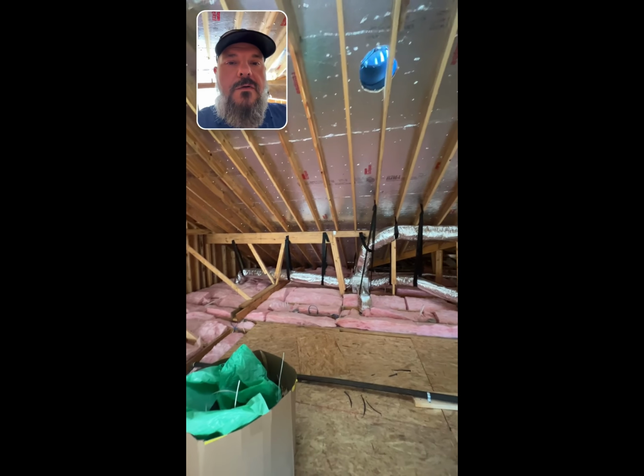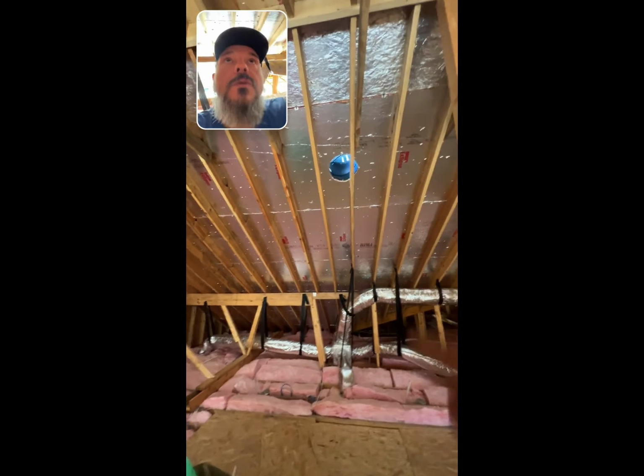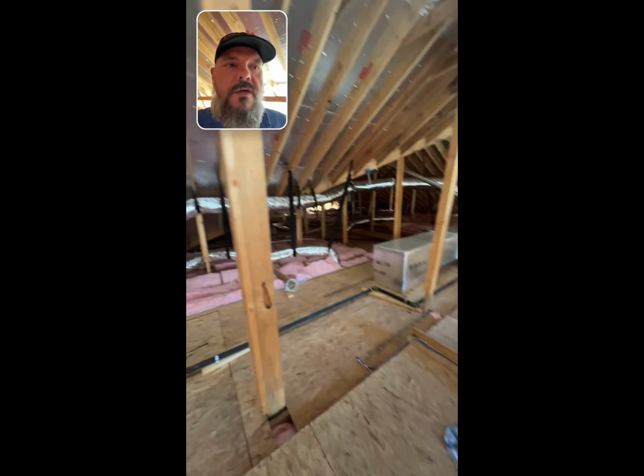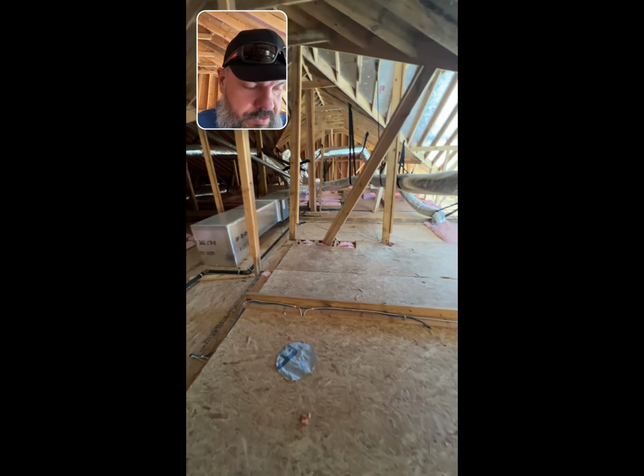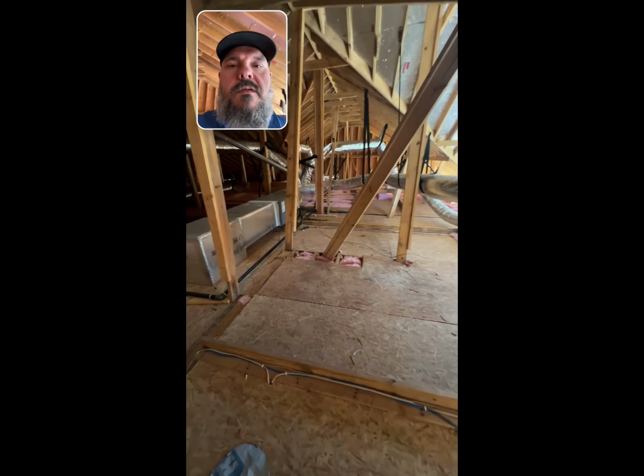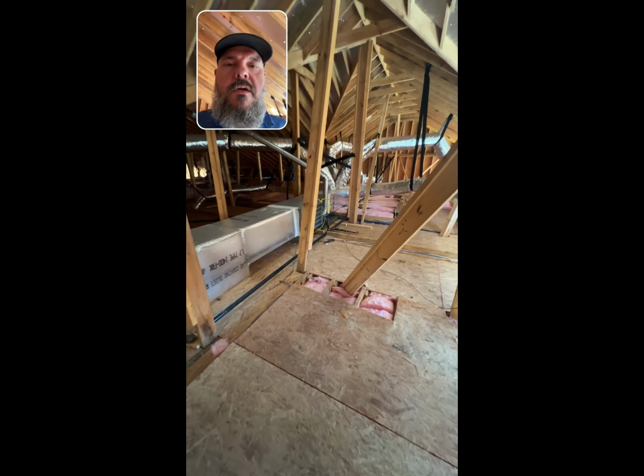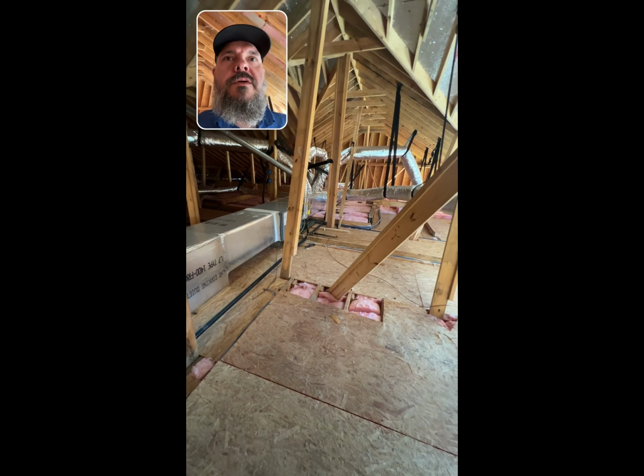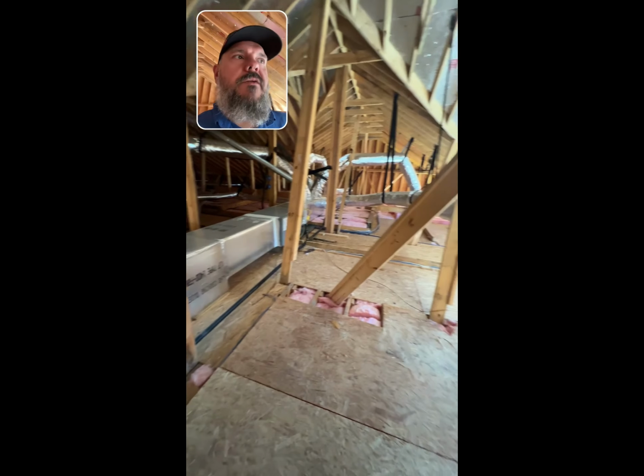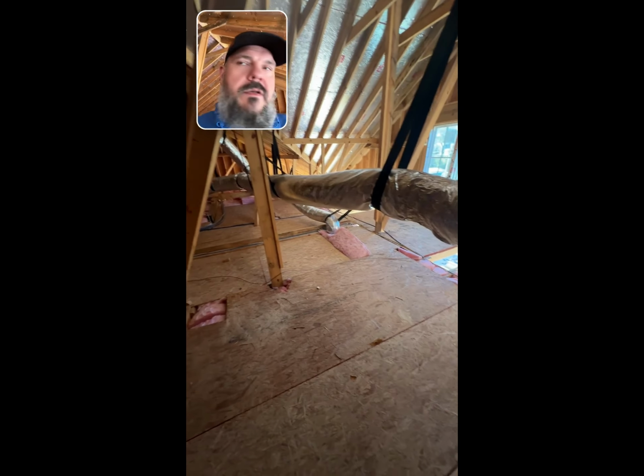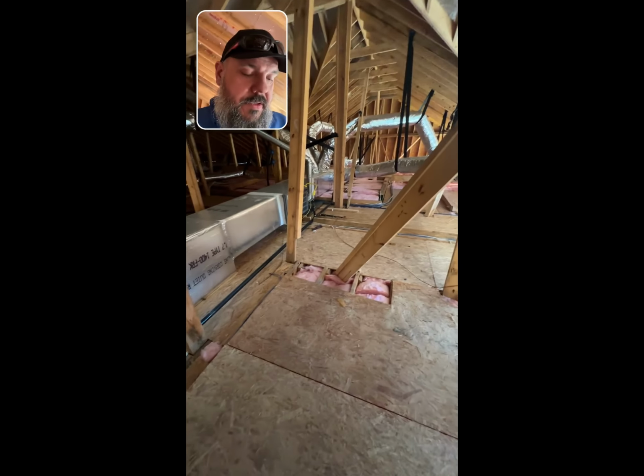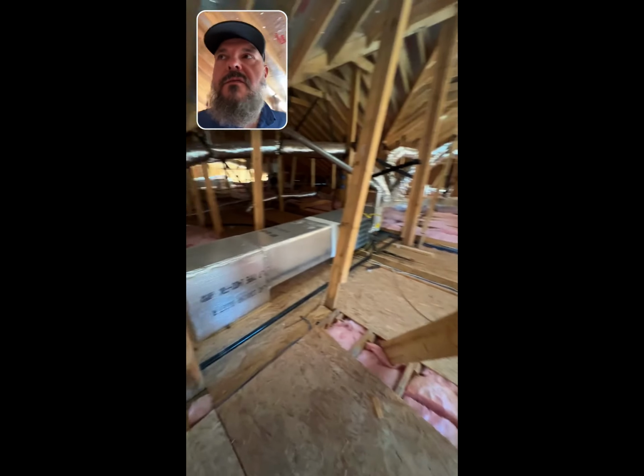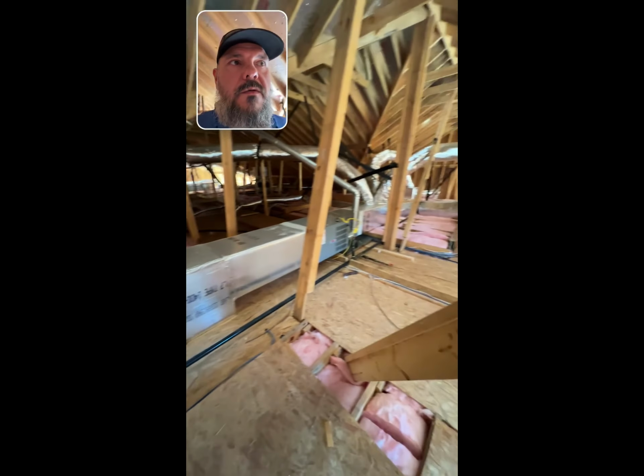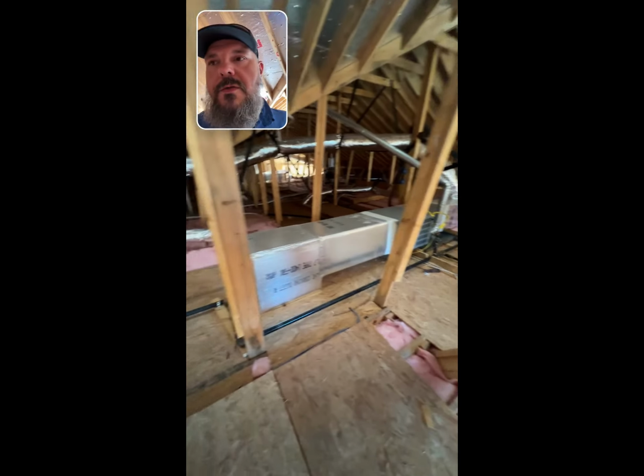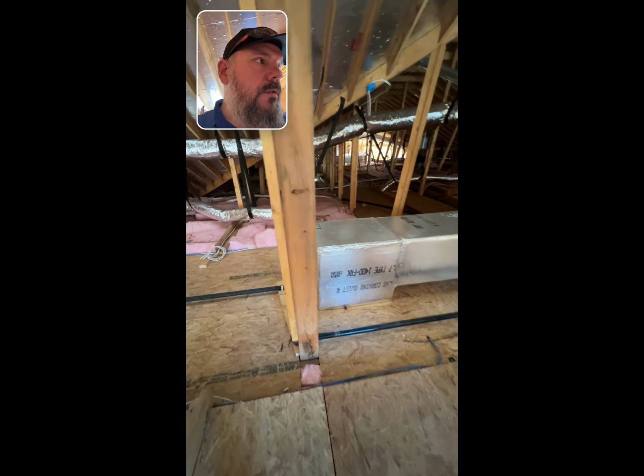We have a vented attic. As I mentioned, we have a radiant barrier roof deck with some turbine vents. So this attic will run fairly cool temperatures, which will cause lower surface temperatures on all the ductwork, which will cause condensation, which will be exacerbated from those cooler temperatures. So this multi-million-dollar home will have condensation issues fairly quickly. The first summer, all of this ductwork will have condensation on it. It will have microbial growth within the first year of operation.